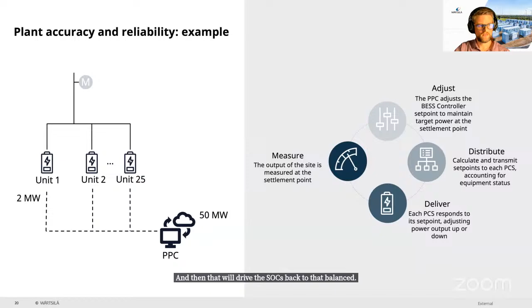Okay, so now we're going to take a closer look at what it takes for a plant to successfully participate in one of these fast frequency markets. In this case, we'll consider a response time requirement of 250 milliseconds. And in this example, we'll consider a plant using separate PPC and BESS controller hardware provided by separate vendors. The process starts at T0 on the left, with the PPC receiving a frequency signal over the local network, usually from a meter located at the point of interconnection. So this is a measurement of the actual grid frequency as seen by that meter.